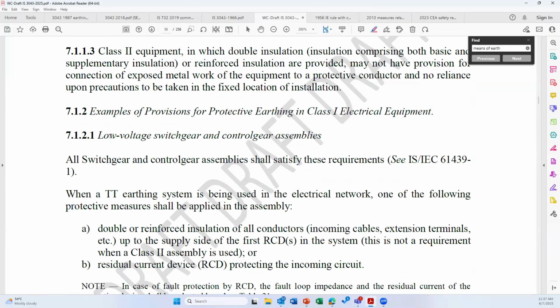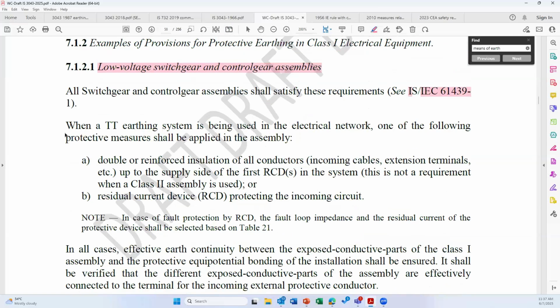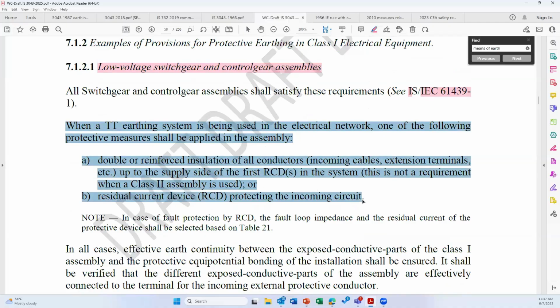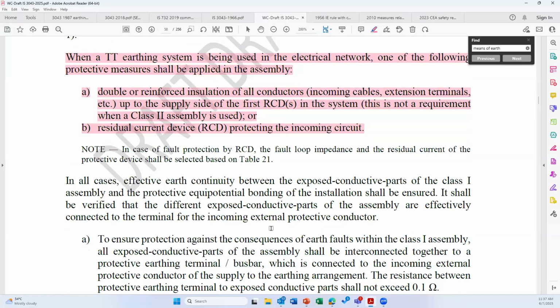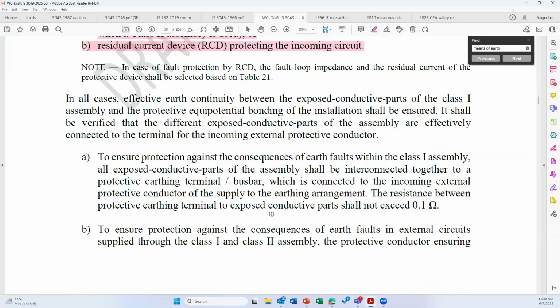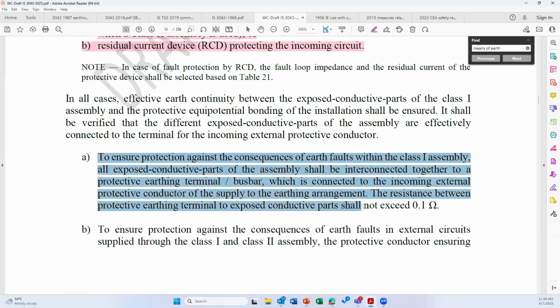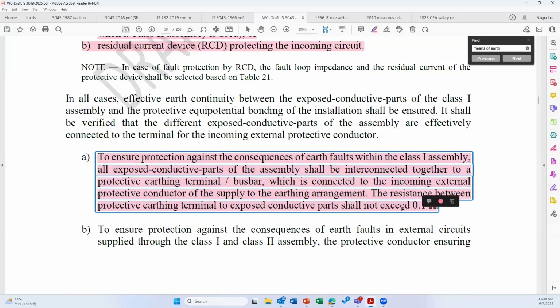Low voltage switchgear and control gear assemblies as per IEC 61439. So here is the standard. The requirement from this particular standard has been included here. In case you have a TT system, what the switchgear and control gear assembly should do. In case of a TN system, what you should do, and what is the resistance required in case of a switchgear and control gear assembly. You can see here the resistance required is 0.1 ohm, about 100 milliohm, within the panel.